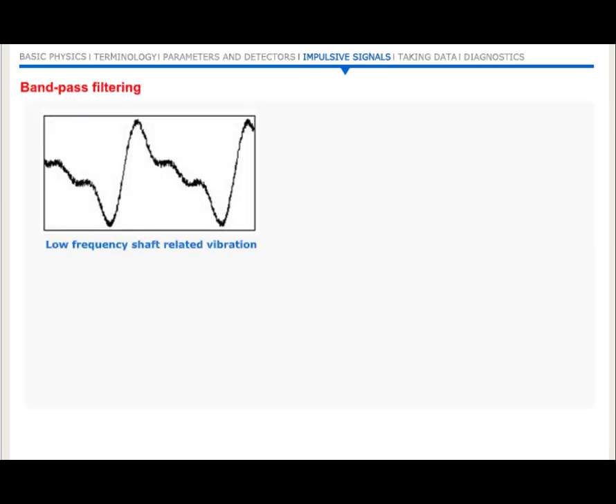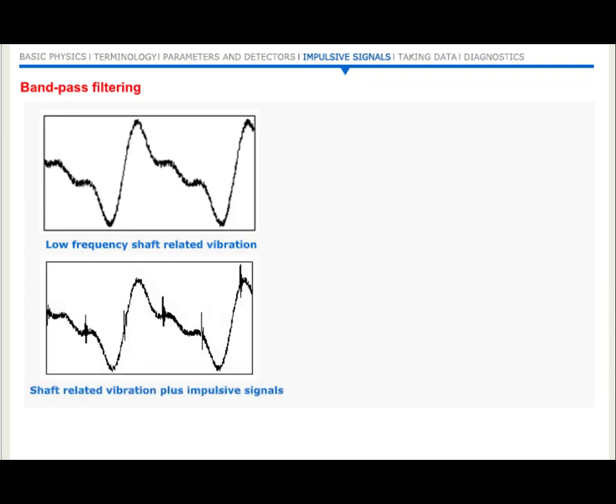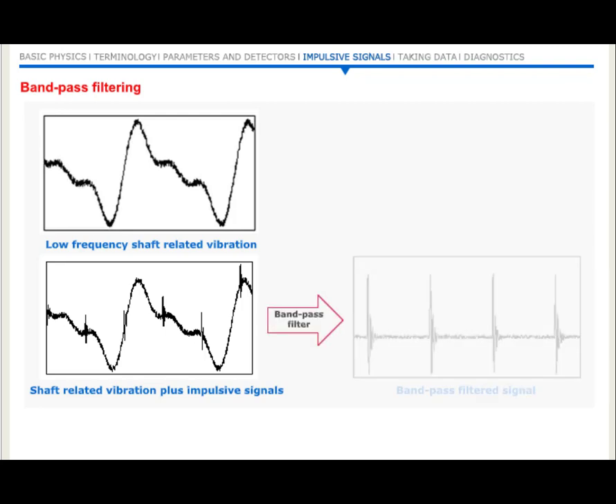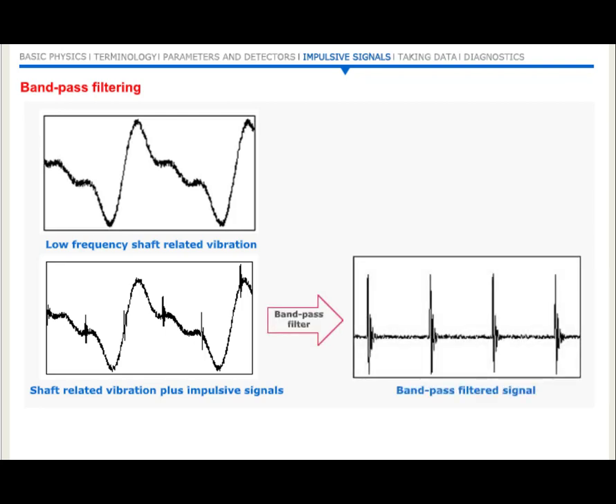Let's take a look at how enveloping works. The illustration here shows a time domain signal, acceleration, resulting from low-frequency shaft-related vibration. In the illustration at lower left, we now see the effect of the impulsive signals resulting from a bearing defect. The first stage of the process involves band-pass filtering of the time domain signal using a band-pass filter that centers on the region of high-frequency energy. The figure on the right above shows the filtered output in the time domain. The filtering process results in a series of spiky bursts of energy, which are the impacts from the rolling elements hitting the defect as the bearing rotates.